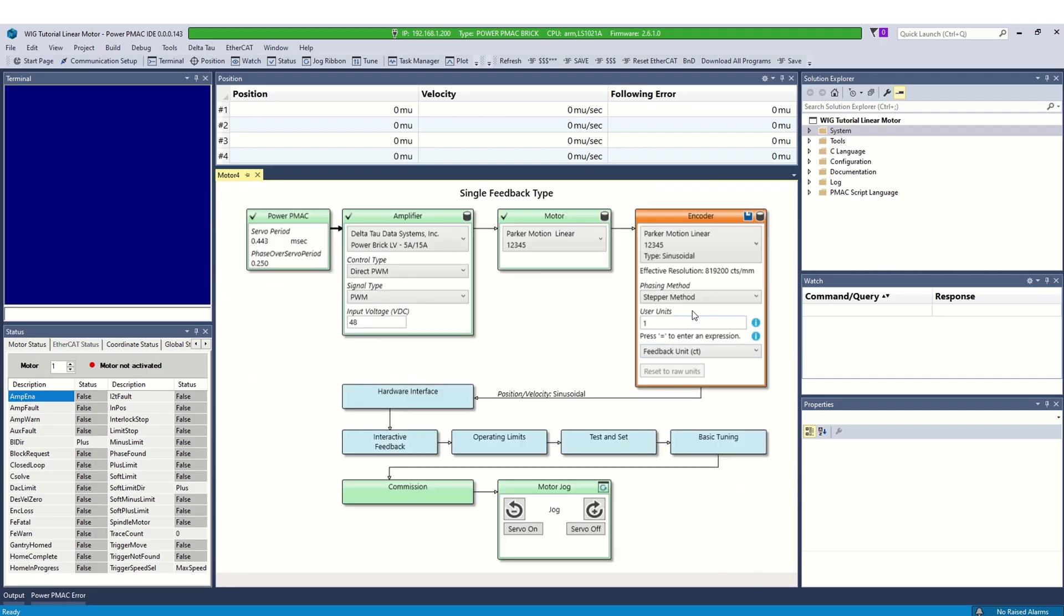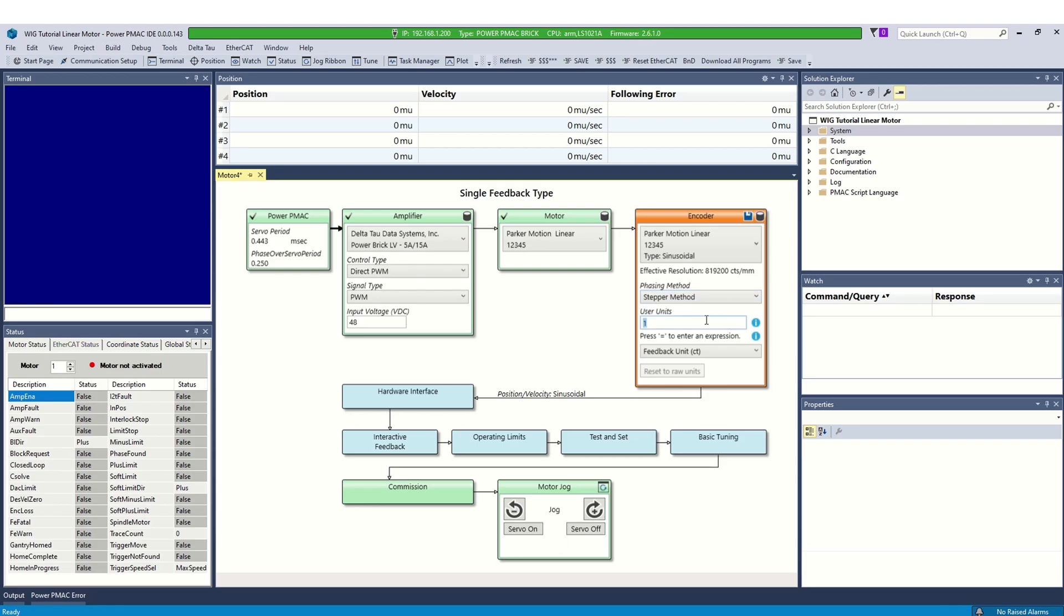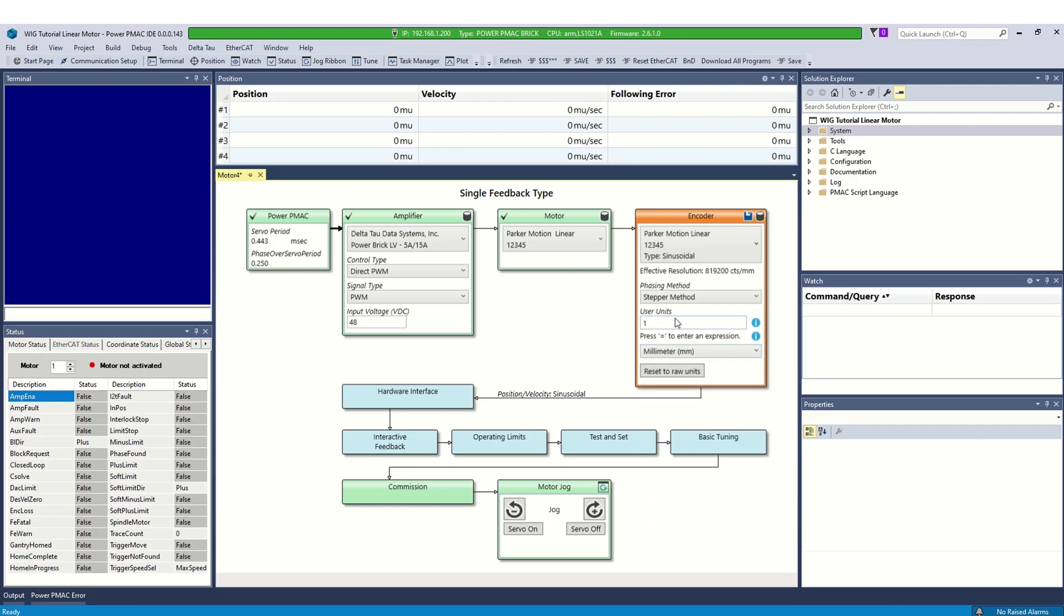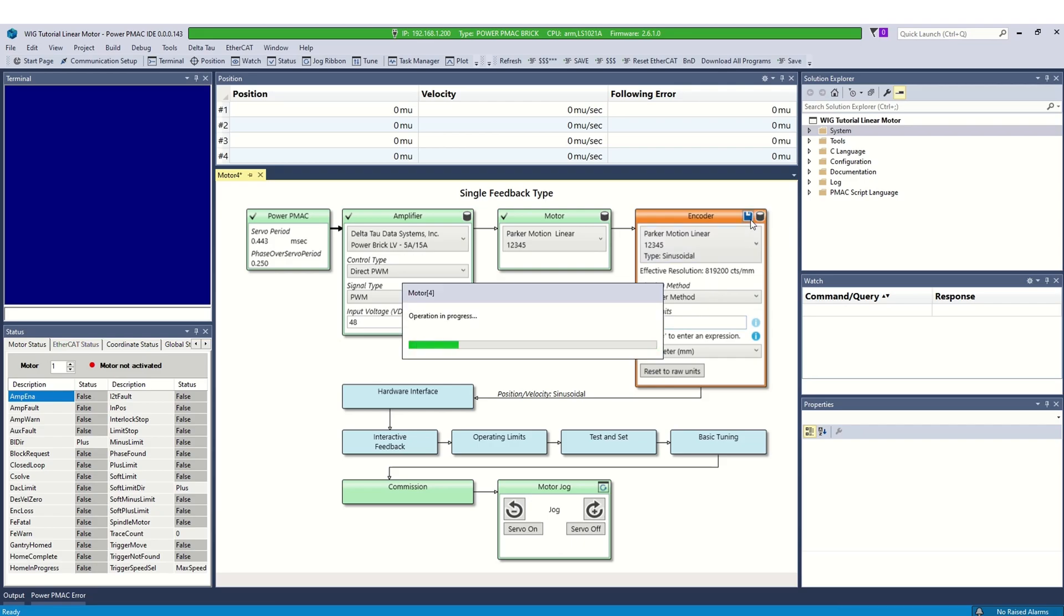Next, we need to define the phasing method for the brushless motor. Refer PMAC user manual to determine correct phasing method for your application. Here we will select the stepper method. Define the user units to scale encoder counts to engineering units. I would like my units to be in millimeters. Select millimeters from drop-down list and set 10,000 counts as 1 mm. Make sure the resolution is correct before moving to the next step. Click save to accept the settings.